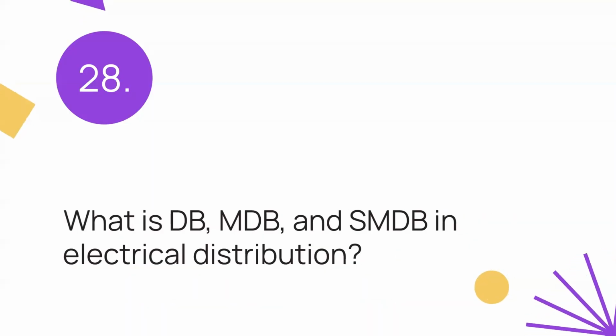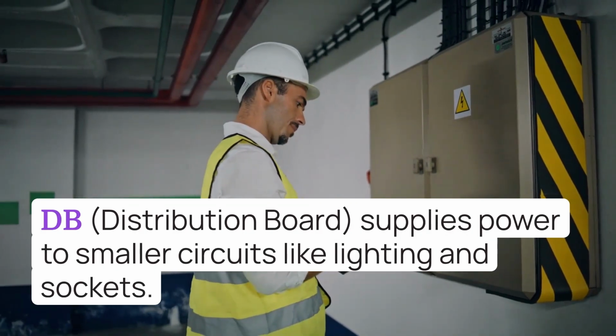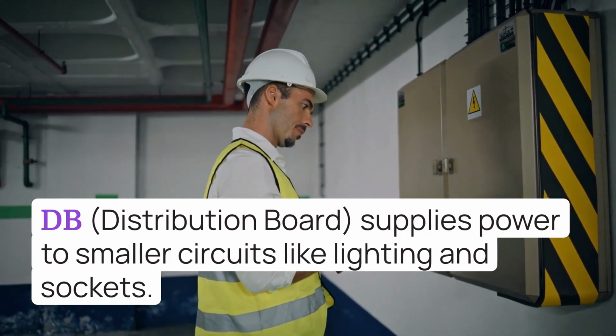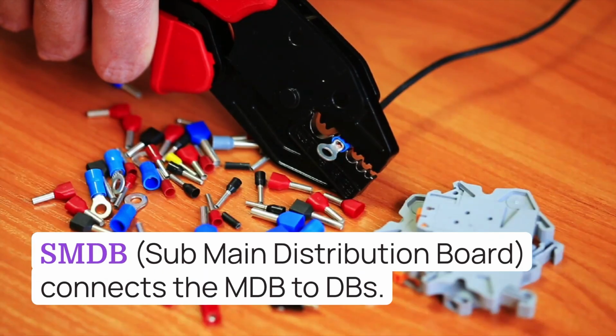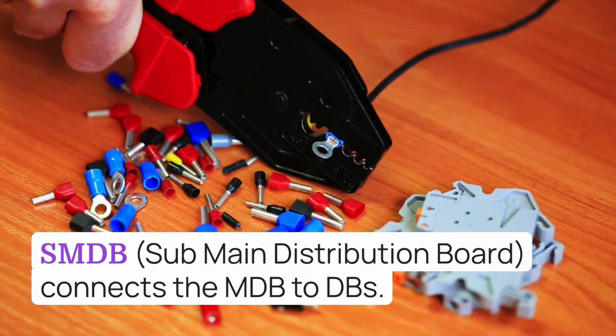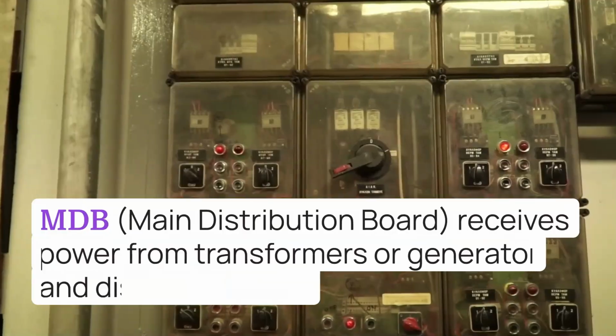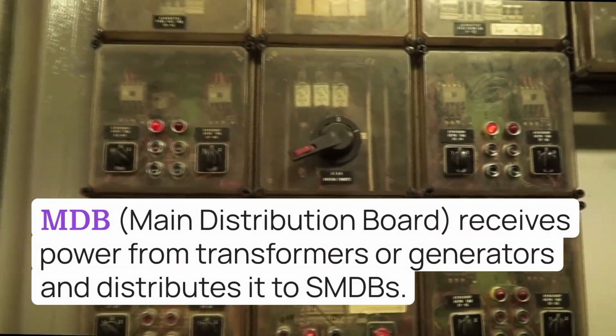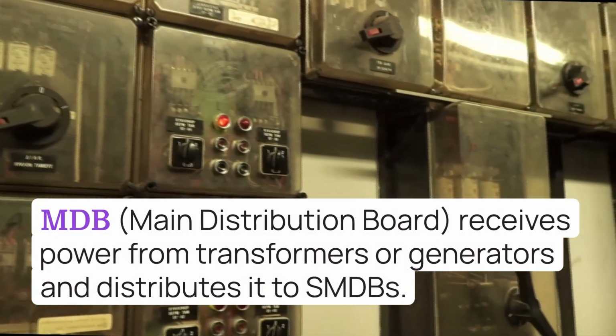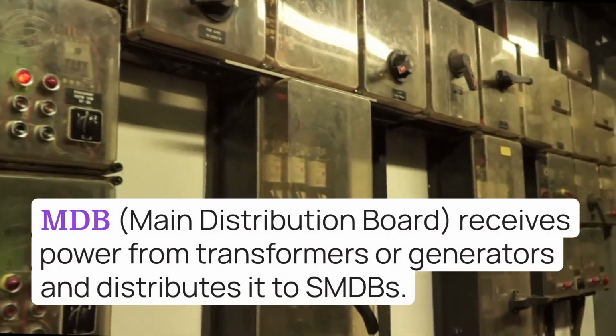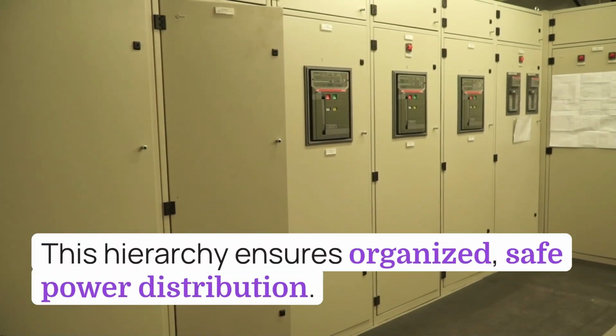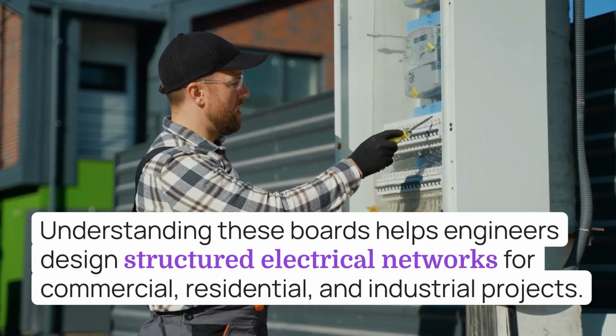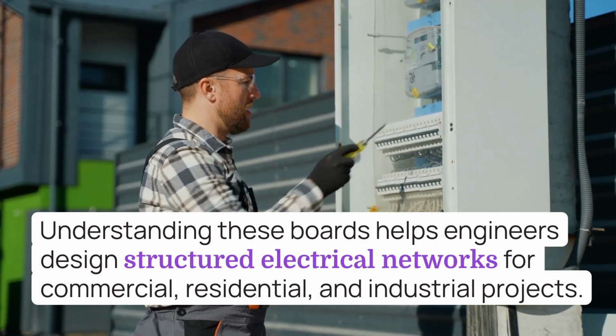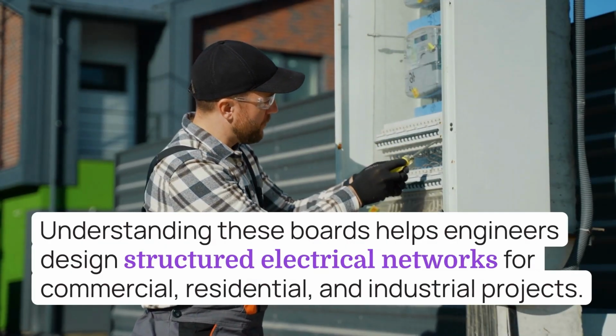Proper transformer selection improves performance, safety, and compliance with electrical standards. 28. What is DB, MDB, and SMDB in electrical distribution? DB, distribution board, supplies power to smaller circuits like lighting and sockets. SMDB, submain distribution board, connects the MDB to DBs. MDB, main distribution board, receives power from transformers or generators and distributes it to SMDBs. This hierarchy ensures organized, safe power distribution. Understanding these boards helps engineers design structured electrical networks for commercial, residential, and industrial projects.